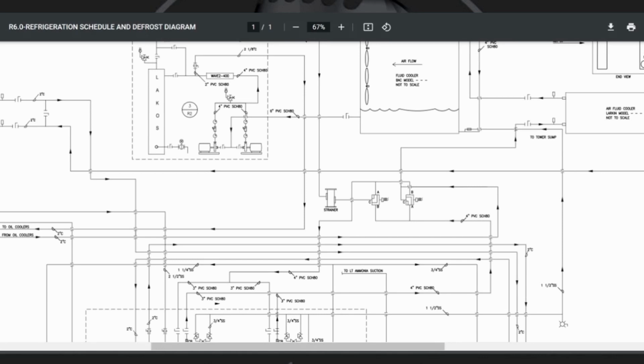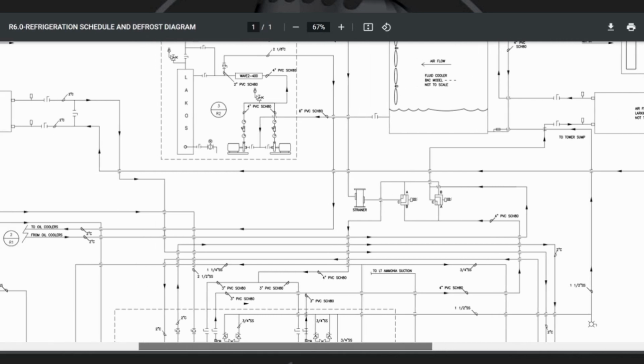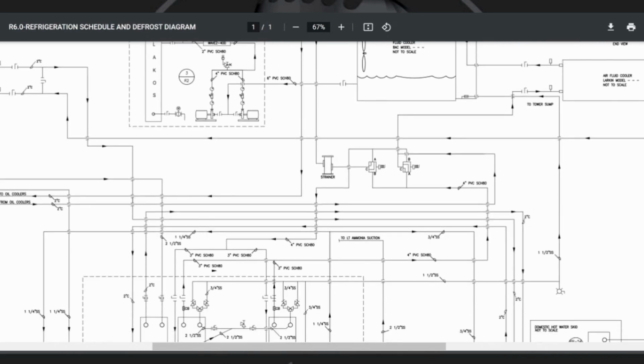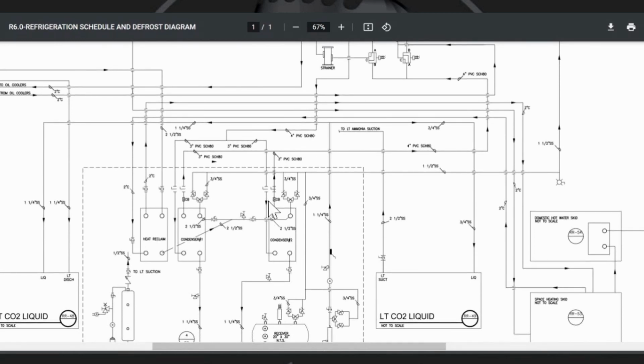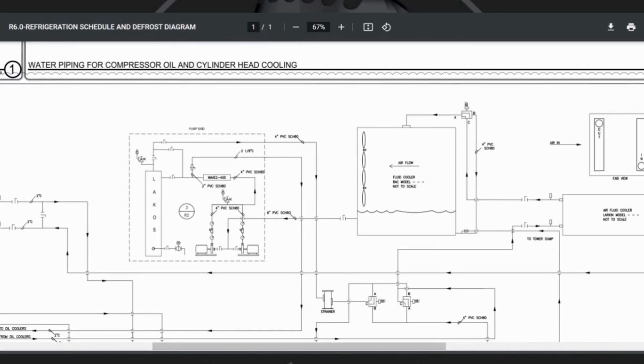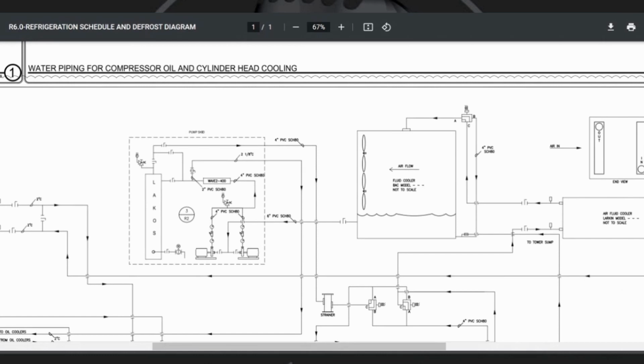The other concern that some AHJs worry about is the pressure relief if you have a high pressure release event. And so you have to do a plume study. We didn't have to on this one. But even if you did, with 135 pounds total charge, the chance of us blowing 135 pounds all at one time is slim and none. But even if it did, and it vents out the roof, this machine room's up on the roof. By the time it dispersed down over the building and got down to the ground, you wouldn't be able to smell it. There's just not enough of it.